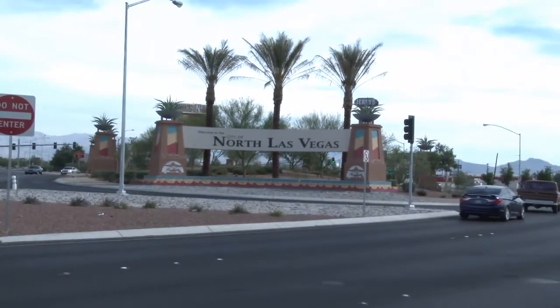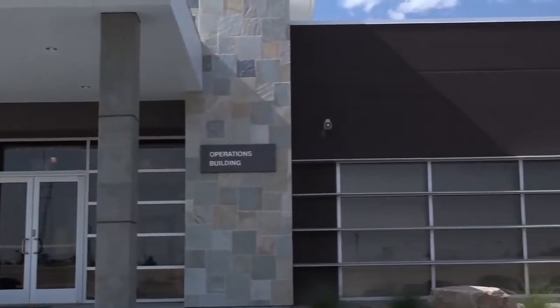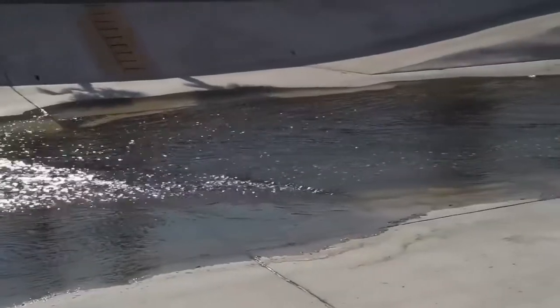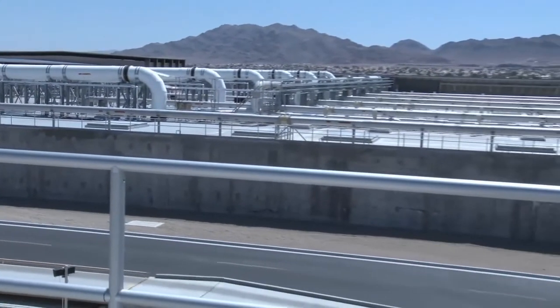Design and construction of a state-of-the-art MBR facility began in 2008 and came online in June 2011. It's a 25 million gallon a day average daily flow, monthly flow plant that can handle peaks of 32 million gallons a day weekly, with hourly flows of 50 million gallons a day. The membranes have 48 membrane modules per cassette, and there are 144 cassettes in the plant for a grand total of about 1.5 million square feet of membrane capacity.